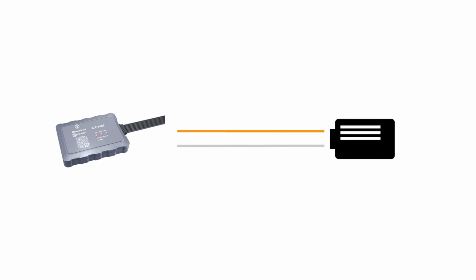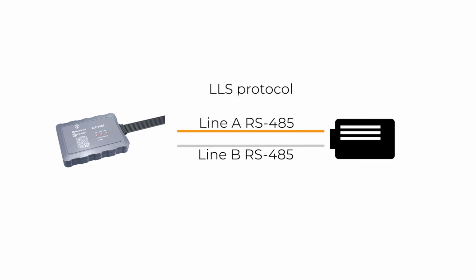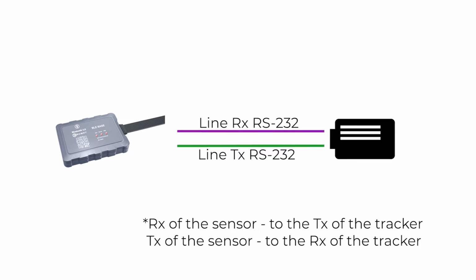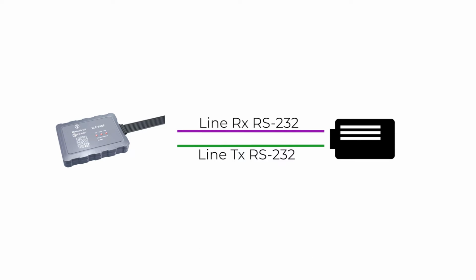The RS-485 interface, just like before, makes it possible for the adapter to respond to requests from a GPS tracker in accordance with the LLS data communication protocol. The same LLS protocol is used if the adapter is connected to a tracker via the RS-232 interface. However, the majority of trackers can only work with just one sensor, and sometimes, for example, if you use Teltonika devices, you need to select the network address 255 for the connection to work.